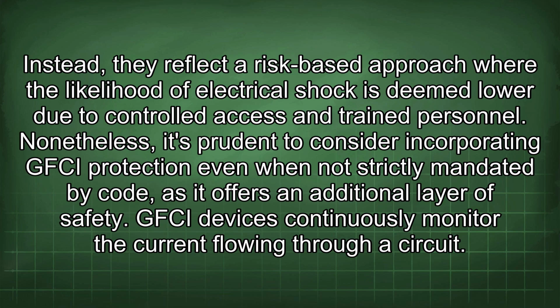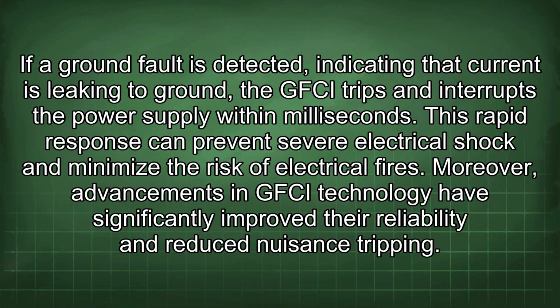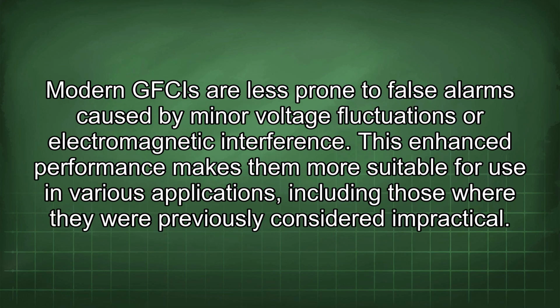GFCI devices continuously monitor the current flowing through a circuit. If a ground fault is detected, indicating that current is leaking to ground, the GFCI trips and interrupts the power supply within milliseconds. This rapid response can prevent severe electrical shock and minimize the risk of electrical fires. Moreover, advancements in GFCI technology have significantly improved their reliability and reduced nuisance tripping. Modern GFCIs are less prone to false alarms caused by minor voltage fluctuations or electromagnetic interference. This enhanced performance makes them more suitable for use in various applications, including those where they were previously considered impractical.